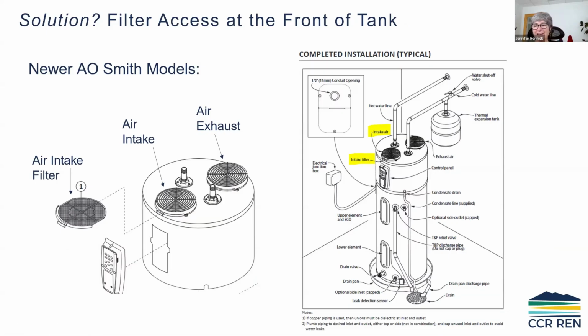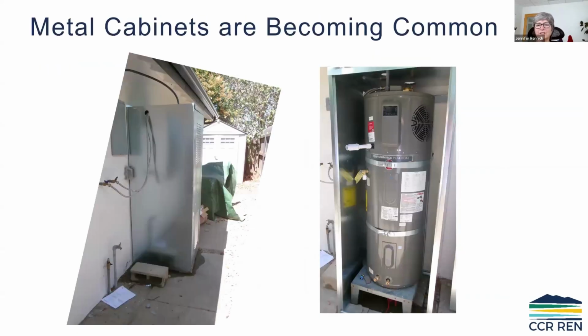Maybe. I saw one recently in a bigger metal shed. Like this one, at least the manufacturer says you need 12 inches of clearance from the outlet port - that port on the right-hand side - between an obstruction. This closet is a bit bigger, so they meet that. It's still a funky closet outdoors, but the one thing it might not meet is showing enough air circulation. The whole metal cabinet's probably super leaky, plus there's an upper louver and a lower louver, so they might meet that code requirement.